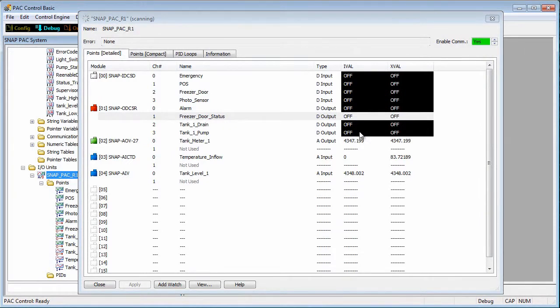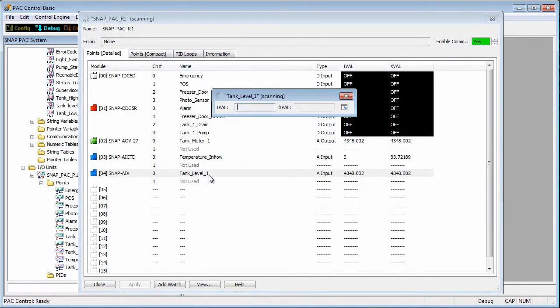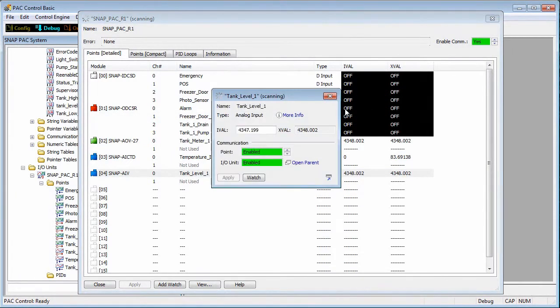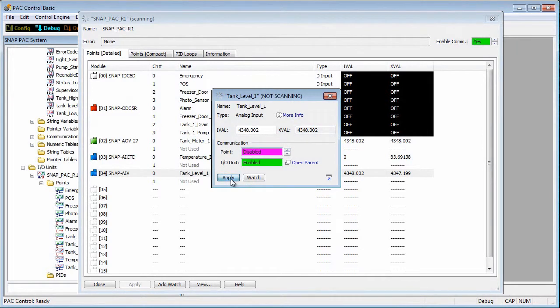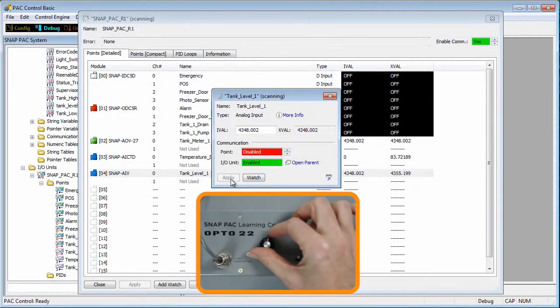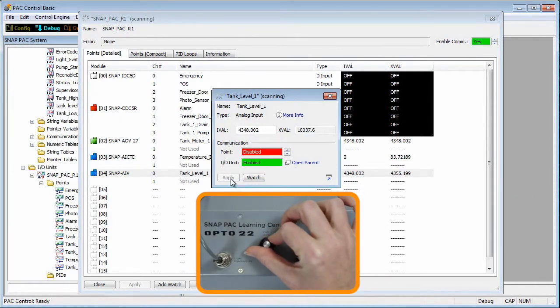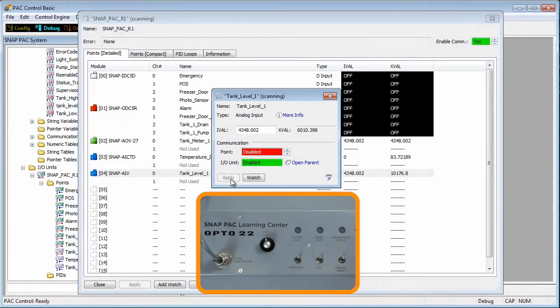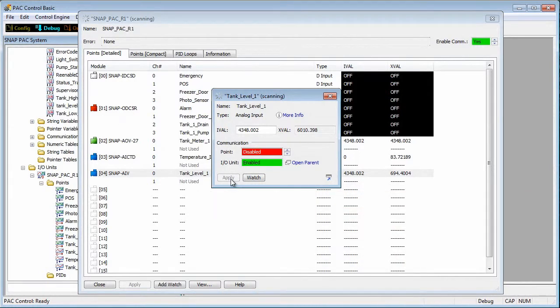I'll select the tank level input, expand the point, and disable communications to the point. This removes the link between the hardware and the software. The XVAL still changes as I turn the potentiometer, but the IVAL is not updated because the point is disabled.